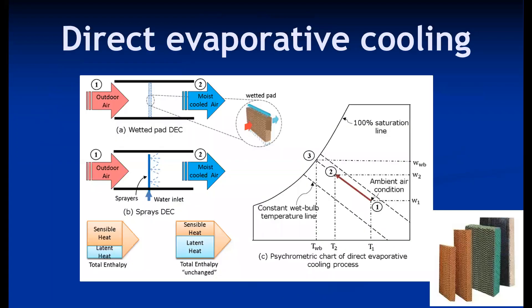This is a direct evaporative cooling system where cooling is achieved with the help of a wetted pad or by spraying water. In direct evaporative cooling, generally cooling and humidification take place. When air is made to flow over a wetted pad where water continuously drips, it gains moisture and at the same time loses heat. The same operation happens if air flows over sprayed water. In ideal cases, this process is called adiabatic humidification, where total enthalpy remains constant.